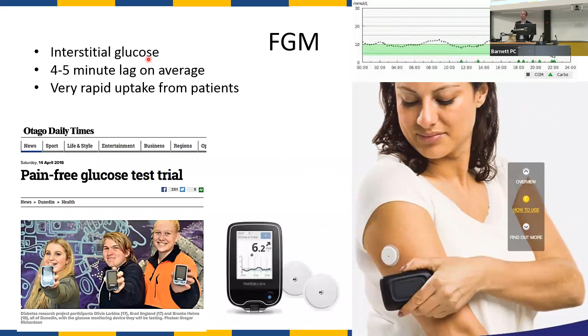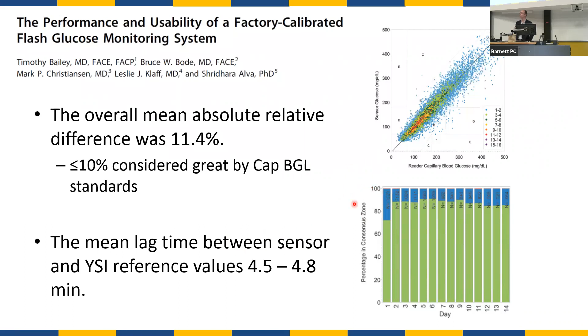But basically, you can see the sensor glucose and the capillary reader reference range here. They're very much clustered together down the center there, so very closely correlated. And again, in this sort of seminal paper on how accurate and successful this was, the mean lag time was about 4.5 minutes. It's also a little bit less accurate on the first day of wear, and that's what we often find. There's something about the immune reaction when you put a sensor in, it doesn't work quite as well.